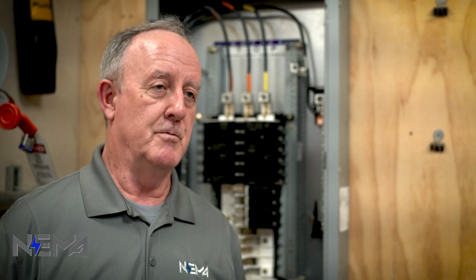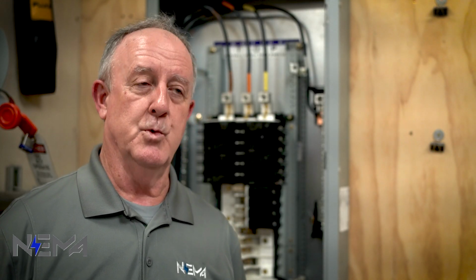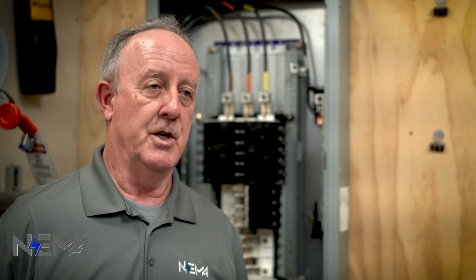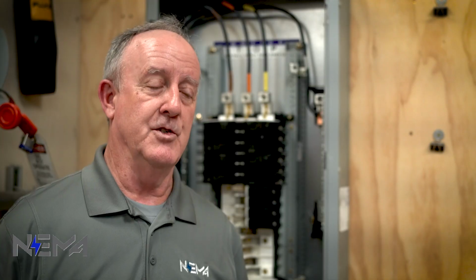So an under-torqued connection can obviously be a problem because you can have a loose connection, which will create more resistance, which in the long run will create more heat, and your connection will fail. But over-torqued connections can also fail in a similar fashion. You can damage the strands on a conductor, or you can damage the threads on a set screw, and over time those connections are going to develop resistance and again more heat, and they will eventually fail.